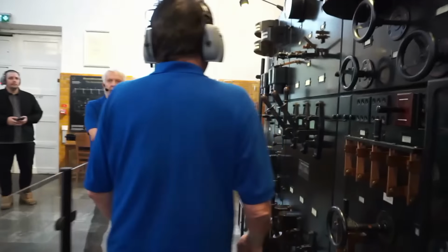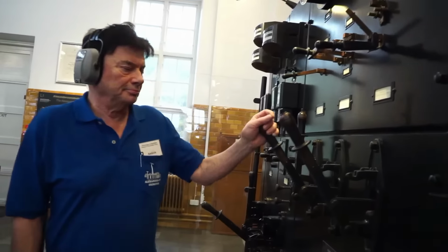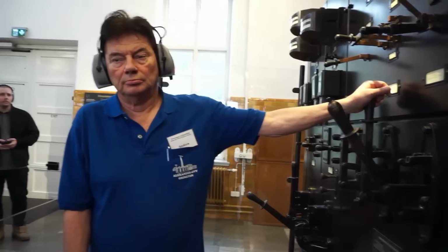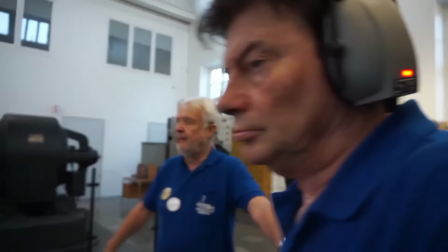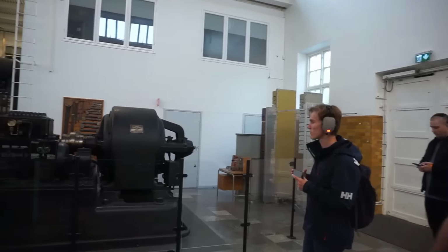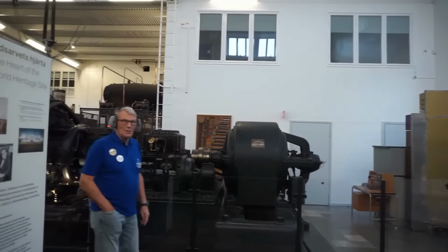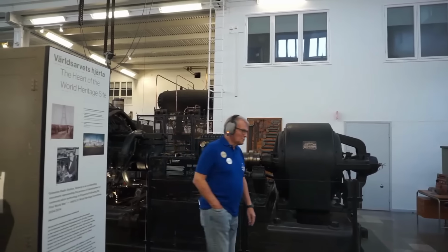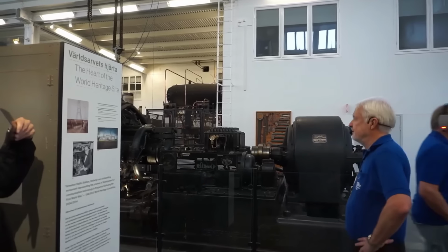we have a persistent signal because we have no oil pressure to the bearings in the alternator. Anders is going back to the emergency switch because we are handling high voltages here.